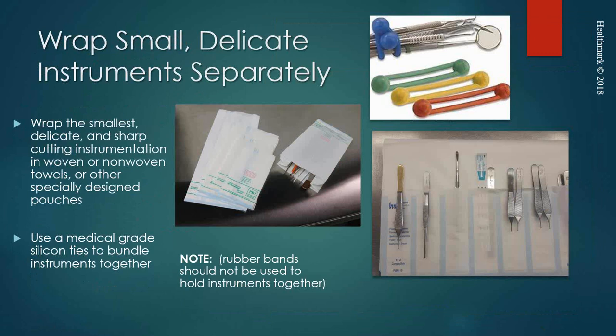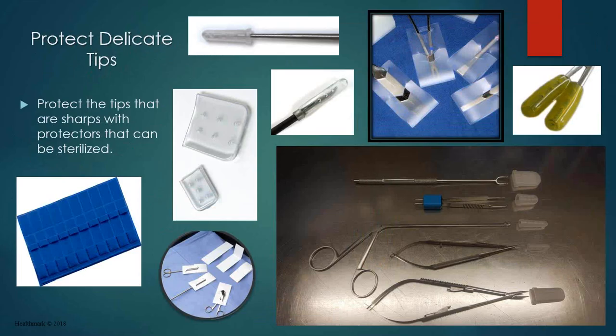Wrap the smallest, delicate, and sharp cutting instrumentation in either woven or non-woven towels or other specially designed pouches, as you can see in the picture. Use medical grade silicone ties to bundle instruments together, like you see on the top right. Rubber bands should not be used to hold instruments together, and I still see facilities using rubber bands, and you cannot do that.